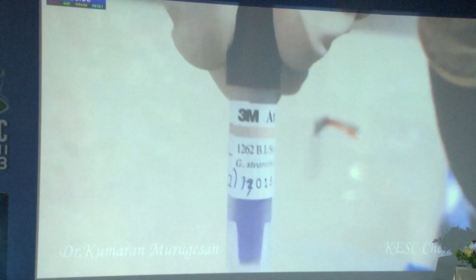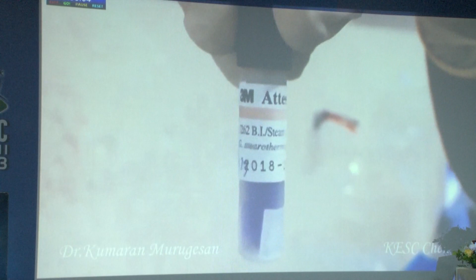And the other most important thing I would like to tell you is the way these instruments are placed inside the autoclave. Vertical placement has been proved to ensure that the steam is able to penetrate inside. The most important validating technique, the biological indicator: same vial, same number, 2 vials, one is kept outside as a control, the other is packed exactly the same way you place your instruments. And this one is placed along with your instruments and goes into the autoclave, whether it's a linen or your instruments. The Bowie-Dick test, as I told you, is not useful for the vertical gravity-based autoclave, but you're using your Class N or your Class B autoclave.